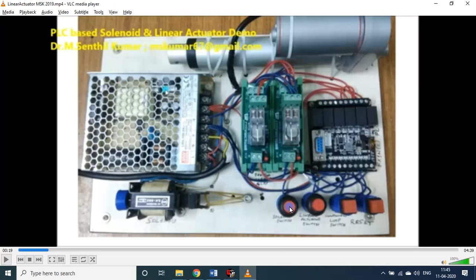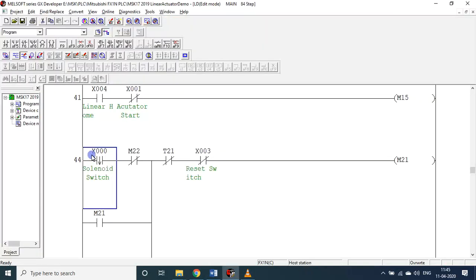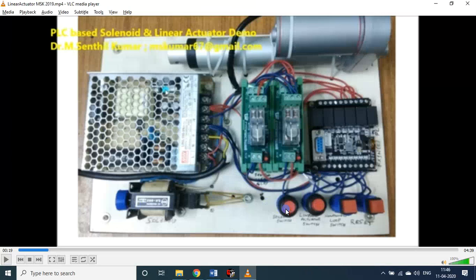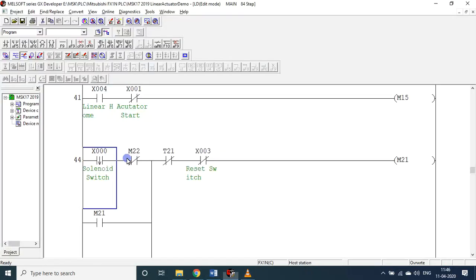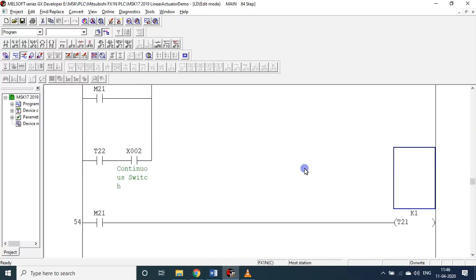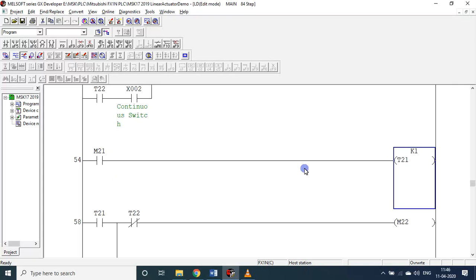For X0 also I used the falling pulse. What is the falling pulse I already told you. Suppose this is the X0 button - I am pressing and holding. I am pressing that means signal started. But M21 will not function because it is not a normal pulse, it is a falling pulse. If I press the rising pulse and I am holding, it is a pulse. In these two occasions this will not function. Only at the time of releasing my finger from the button I get the falling pulse. That time only this line will be executed.